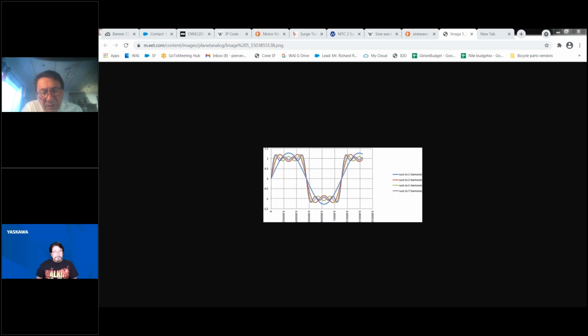We're giving you an update on where we are in terms of the submersible pump motor applied on a VFD, and we've had an unacceptable level of issues - certainly unacceptable to the motor manufacturers, because a lot of it is happening within their warranty periods. Basically, the goal at Yaskawa is that a motor will run as long on a VFD as it will on a contactor. That's a general goal, though probably not technically sound, because varying the speed of the motor versus running it across the line all the time is not a fair comparison.